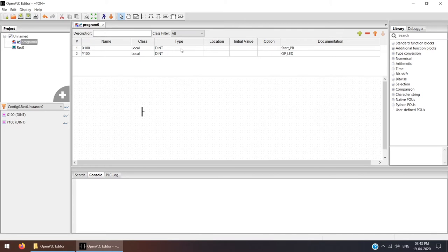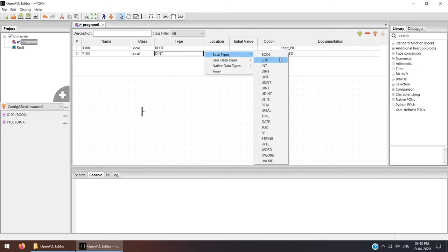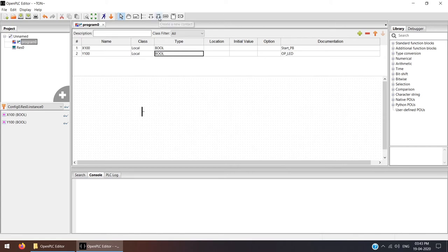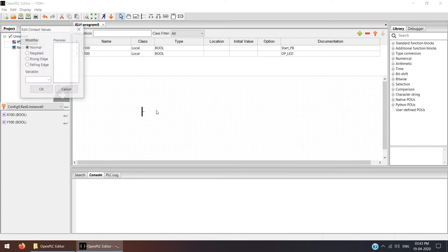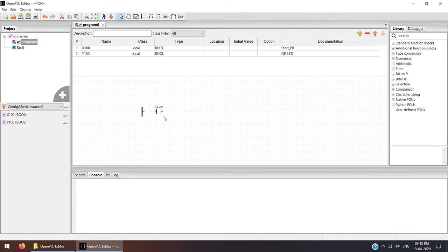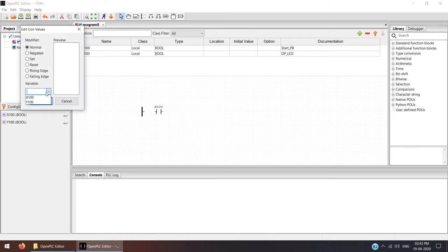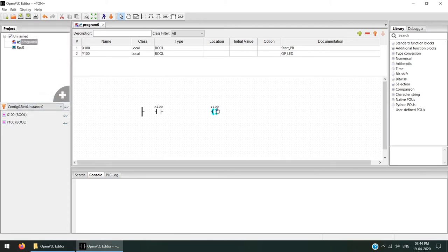I made a mistake here — the data type. I forgot to change it. Make it base type boolean. Here also change it to boolean, otherwise you won't get this option. Click over here again, add new contact, and now you're getting the variable X100. Keep in mind: always change the type to boolean, otherwise you will not get the name of the variable in the list. After that, we need to add one output coil. If the variable is not visible, check the type — it should be boolean. Then Y100.